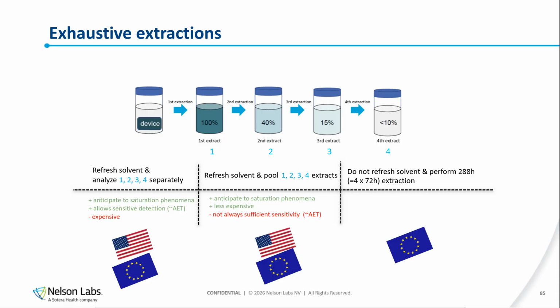And then we have the pooling in the middle. This also anticipates the saturation phenomena and is less expensive, but the AET gets lower and lower the more cycles you have. And then the last one, which is not allowed by the FDA, is to not refresh the solvent each time. It's just a one-step extraction where, in the example that I've shown, you do 4 times a 72-hour extraction, which is 288 hours. You just add the solvent once and you do a one-step extraction for 288 hours.